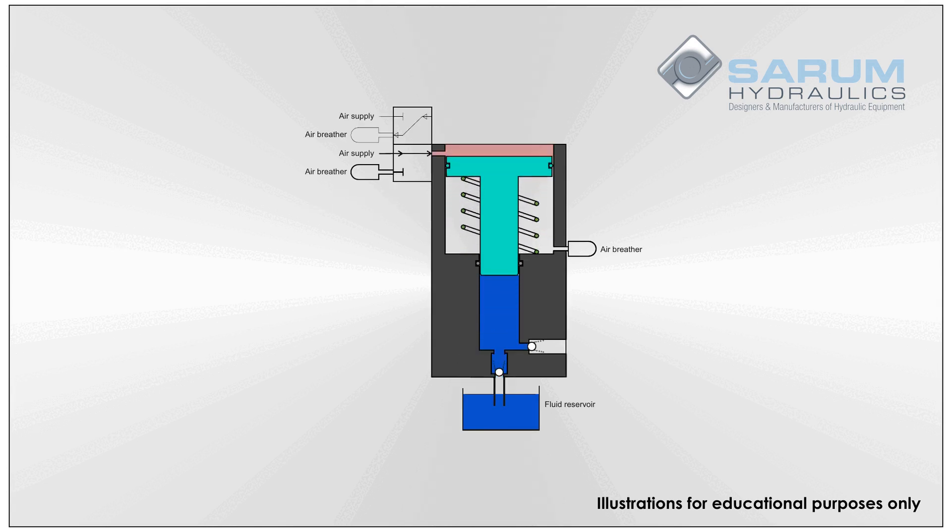Air driven hydraulic pumps cycle automatically. When compressed air is first applied to the pump, it will cycle at its maximum speed producing maximum hydraulic flow. At this stage, the pump is acting as a transfer pump filling the pressure receiver with liquid.